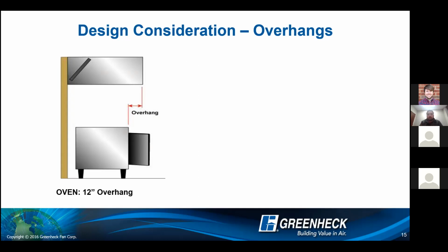We have our airflow sized at 275 per foot for the heavy hood that we're talking about, and we go right from there. But what I would like to call your attention to is, keep in mind when you're designing a system that has large combi ovens or convection ovens, Greenheck would recommend a minimum overhang of 12 inches from the front of that appliance.